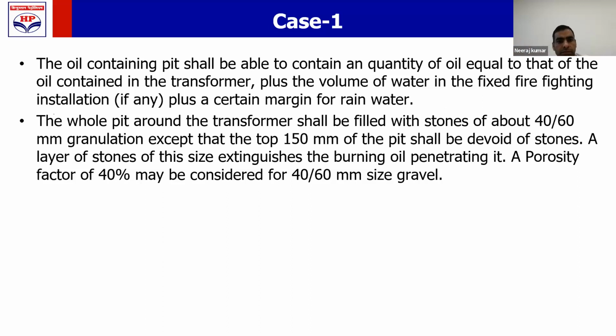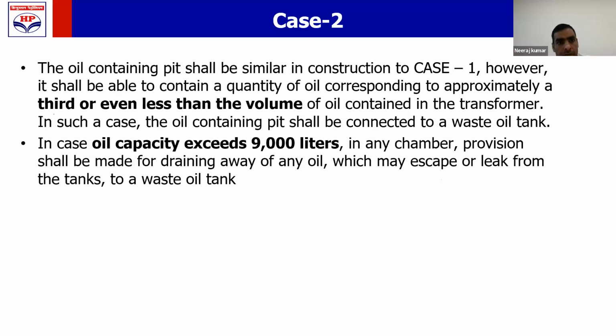meet this requirement. You are not able to provide an oil containing pit which is equal to the capacity of your transformer. Then what do you do? Then comes case 2. Then you should provide an oil containing pit of minimum 1/3 capacity of your transformer oil. Even उससे कम भी चलेगा, 1/3 का तो ट्राई करना है. So if you provide an oil containing pit of capacity less than 1/3 or even less, then what will we do?